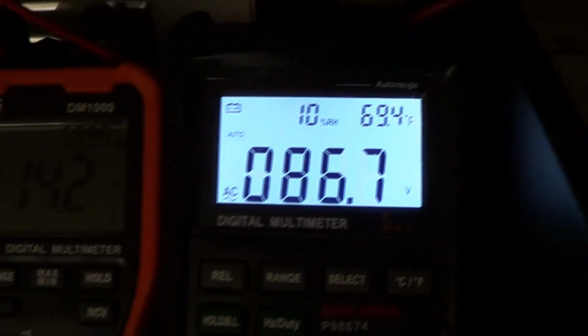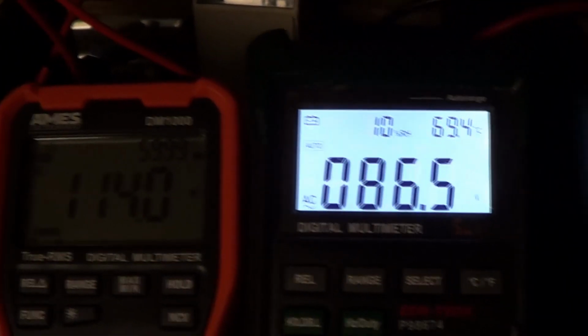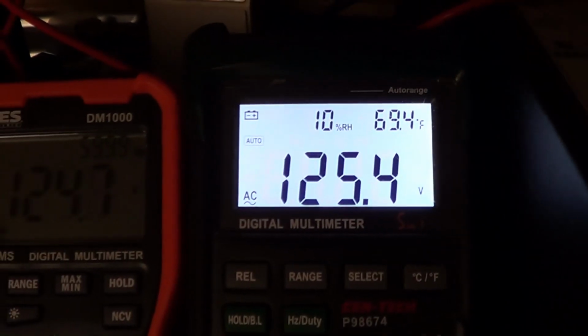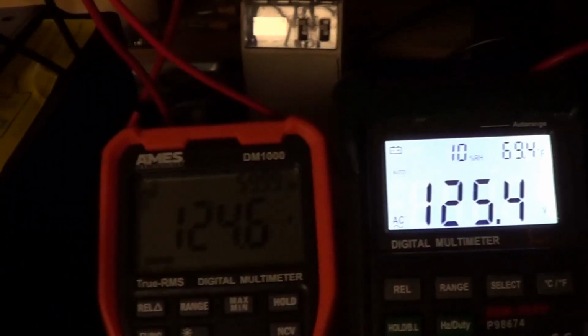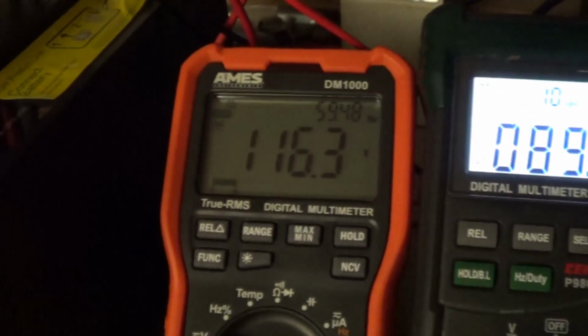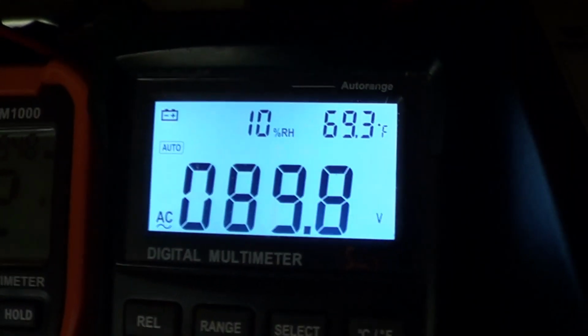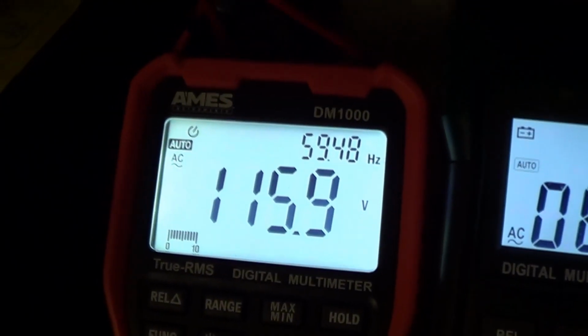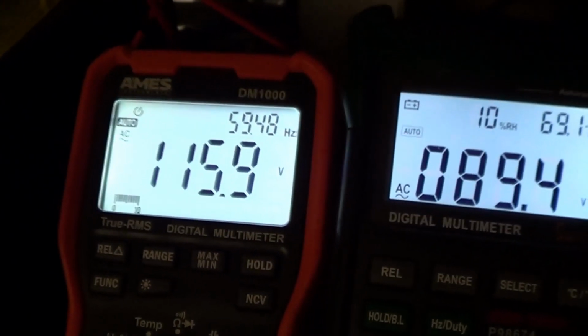But when the inverter kicks on and the wave shape changes, the 98674 reads way, way low. In fact, let's actually see that again. We'll force the UPS over to its battery. All of the true RMS multimeters are reading accurately, some a bit more so than others, while the poor 98674 is reading way low. So the Ames DM1000 is definitely, as expected, a true RMS capable multimeter.